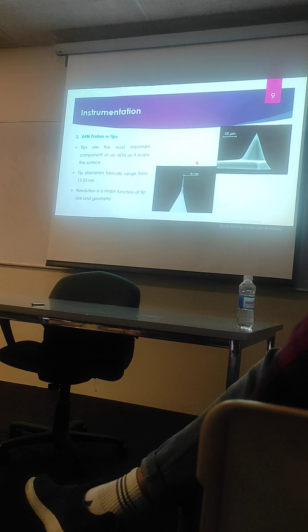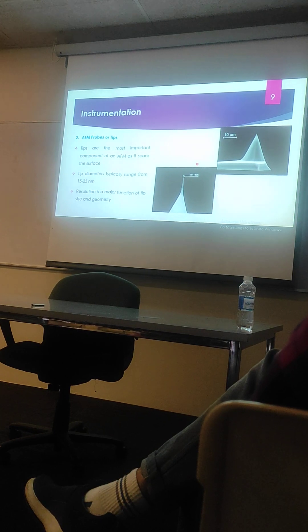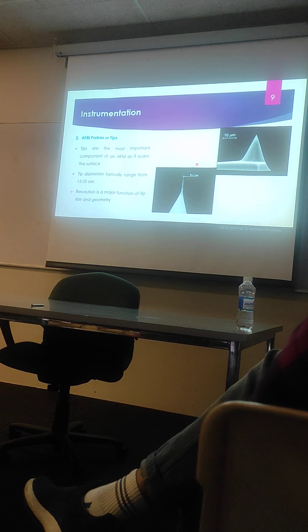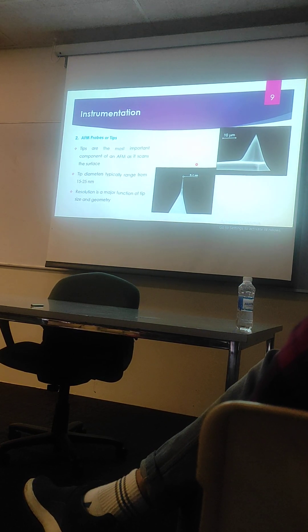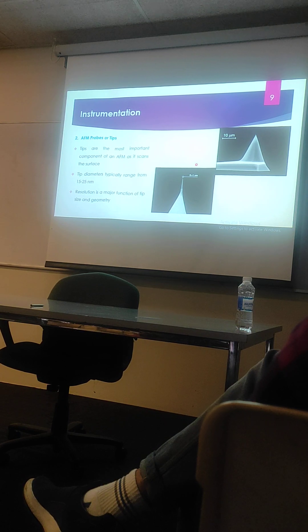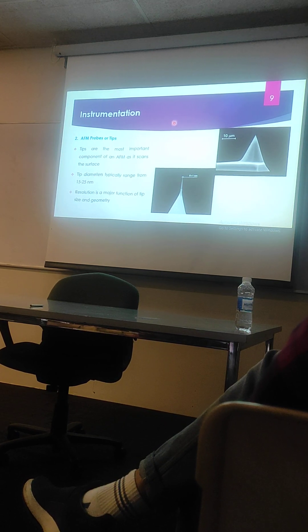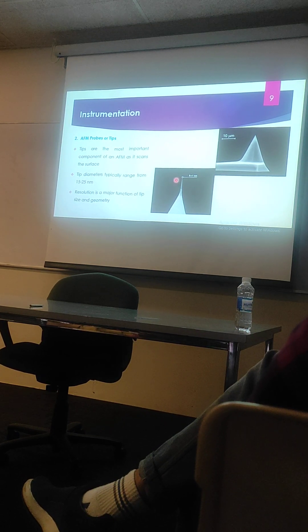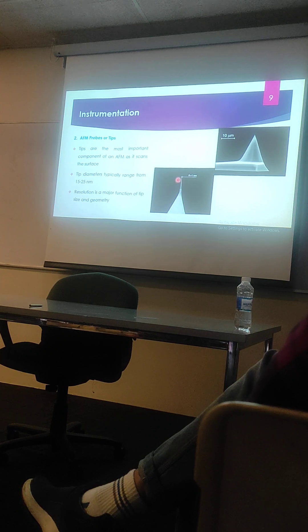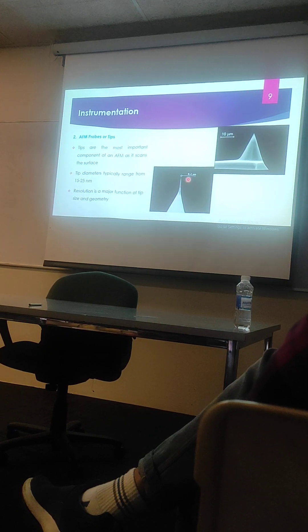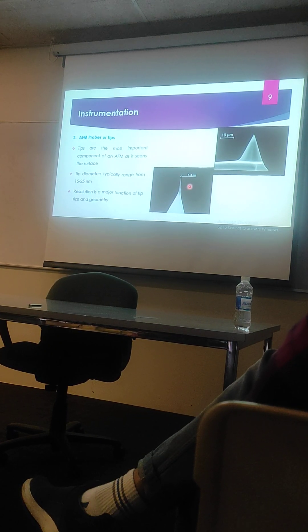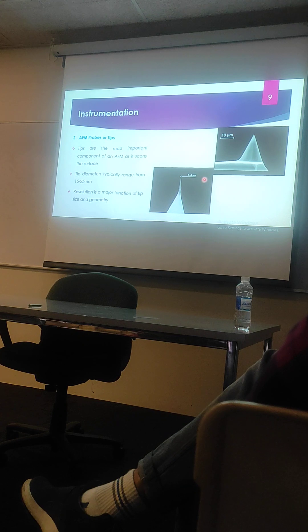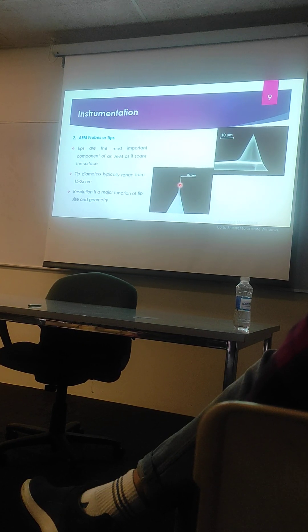One of the important components of atomic force microscopy is the probe that is used for scanning the sample surface. Its dimension ranges between 15 to 25 nanometers. The resolution of the image that we get is actually a function of the size of this probe or tip.